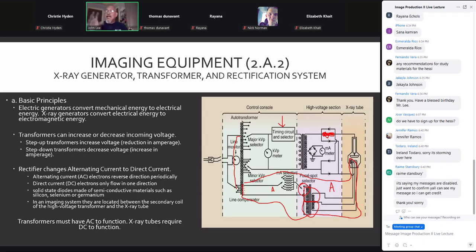The timer is located in the tube circuit, which is all of this up here. The reason the timer is in the tube circuit is because we want to control the production of X-rays, not thermionic emission. We want thermionic emission happening before and even maybe slightly after the exposure is done, just to make sure we get all the radiation we can out of the exposure. So the timing circuit is located in the tube circuit. It controls the X-ray tube being on, all right? The filament circuit takes care of the filament.